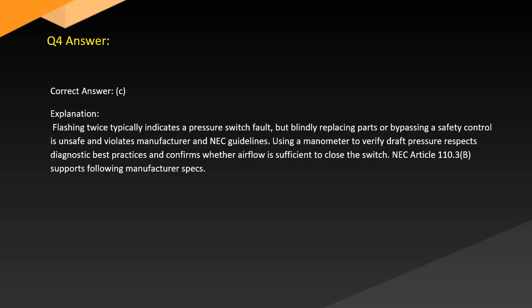Answer. Correct answer: C. Explanation. Flashing twice typically indicates a pressure switch fault, but blindly replacing parts or bypassing a safety control is unsafe and violates manufacturer and NEC guidelines. Using a manometer to verify draft pressure respects diagnostic best practices and confirms whether airflow is sufficient to close the switch. NEC Article 110.3(b) supports following manufacturer specs.